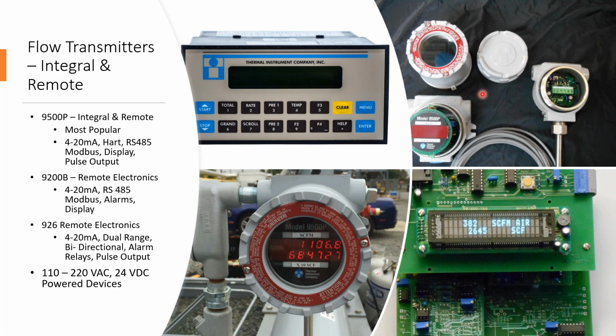So in a remote environment, maybe you've got a pipe that's running along the ceiling or running high, or this measurement needs to be taken high in the chimney stack. The nice thing about the remote is that you can put the sensor where it needs to go, and then with up to 1,000 feet of cable, you can drop the actual transmitter unit down to some place where an operator can read it, can reset a totalizer, can check connections, and so forth. All of our units deliver a 4 to 20 milliamp output. We can accommodate RS-485 Modbus. We can do pulse outputs. We can do HART outputs on the 9500P. And we also offer on the 9500P a 2-line display like you see here.